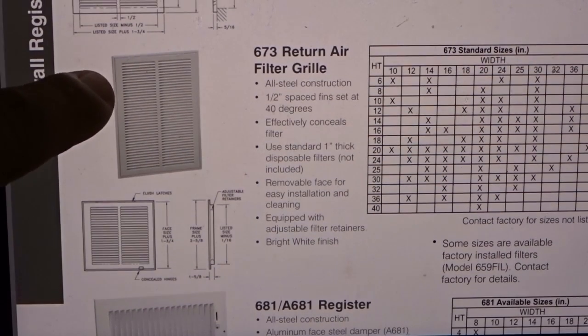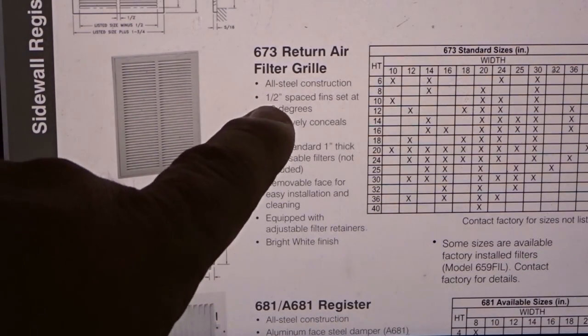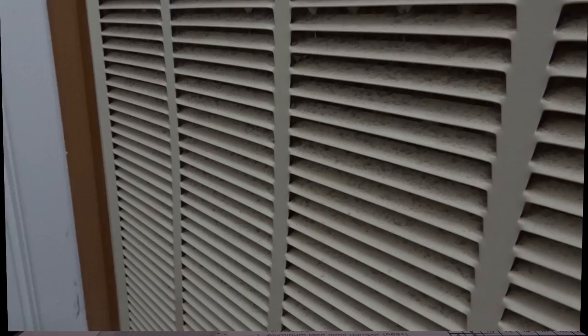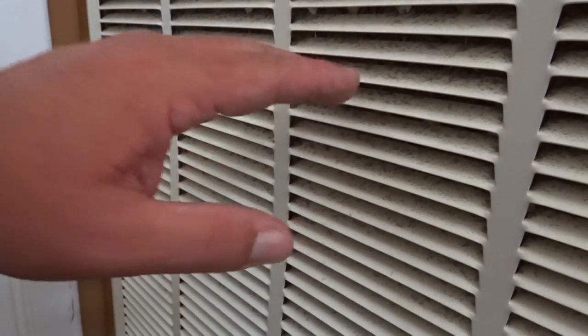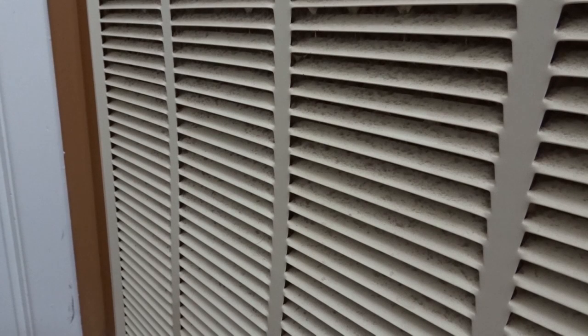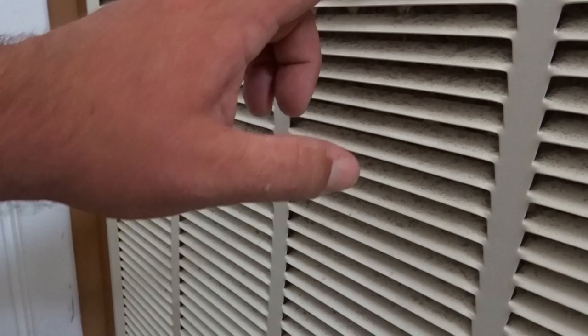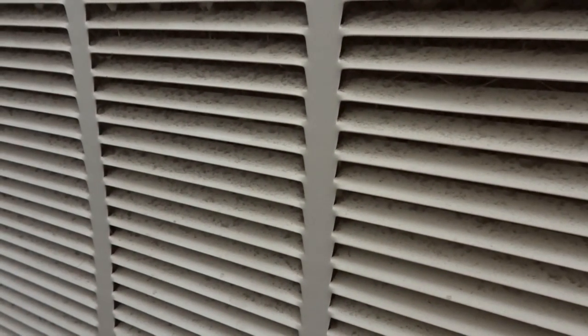We have now the 673 return air filter grill — all steel construction, 1/2 spaced at 40 degrees, which matches up closely with what I have here. 40-degree fins, and you can see the fins themselves transition over there and they're spaced at 1/2 inch. Now you can hear the machine is running, and we have these fins — they're almost at a 45-degree angle, which kind of meshes with what it says about the 40-degree fin angle, and they're at ½-inch intervals. Usually older grills have a closer interval and they're 1/3 spaced. So there's our grill, and we're going to go back to the engineering data to find our free area for this 30 by 20 grill.